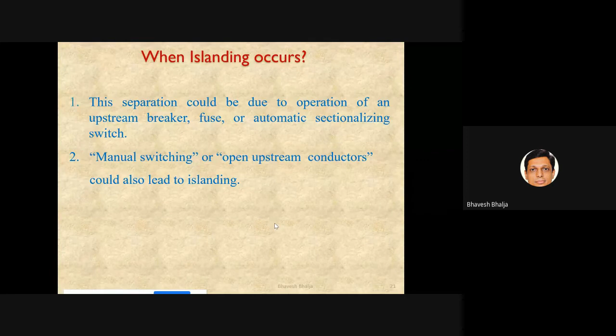So the next topic is when islanding occurs. When there is an opening of the upstream breaker, or opening of a fuse, or opening of some sectionalizing switch, then islanding occurs. Or when manual switching is done by the person working in the substation, then also islanding occurs. So there are two possibilities in which islanding occurs.